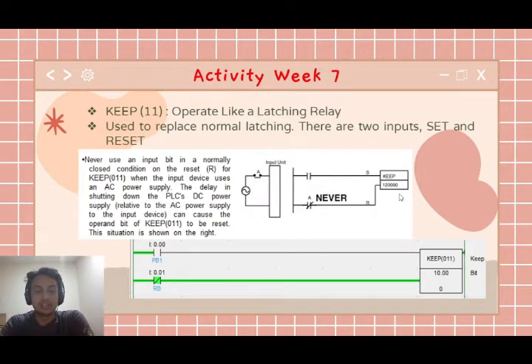The operation of KEEP 11 operates like a latching relay. It is used to replace a normal latching relay, and there are two inputs, set and reset. Never use an input bit in a normally closed condition on the reset for KEEP. The input device uses an AC power supply.